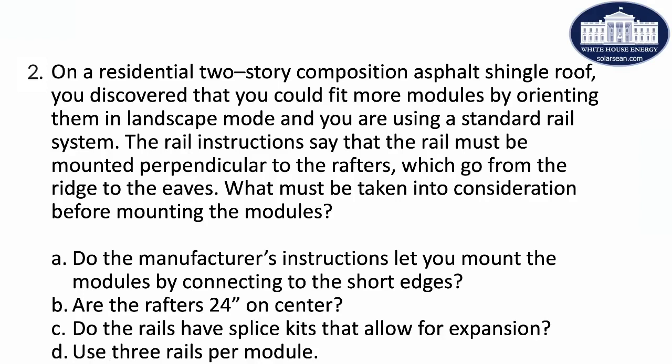It matters how strong the rafters are, how strong the rails are, how strong the wind is. And usually what's going to happen is you get into the installation manual for the racking system, and then you look up your wind zone, you look up your rafter and your rafter spacing and your rafter span, all that kind of stuff. And then you figure how often you have to attach to a rafter. So this is not the answer that we're looking for. I don't think A is much better than B. Let's look over at C.